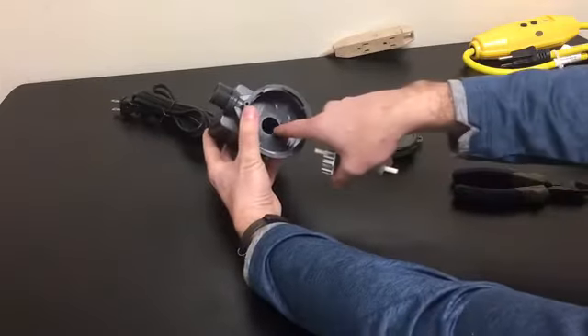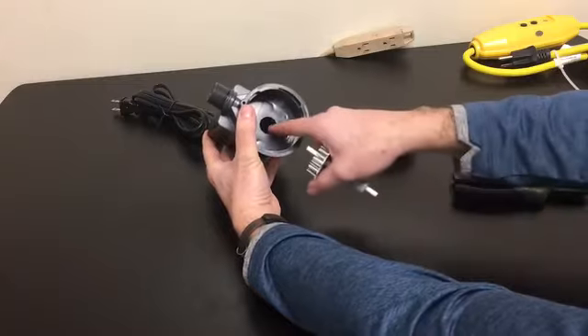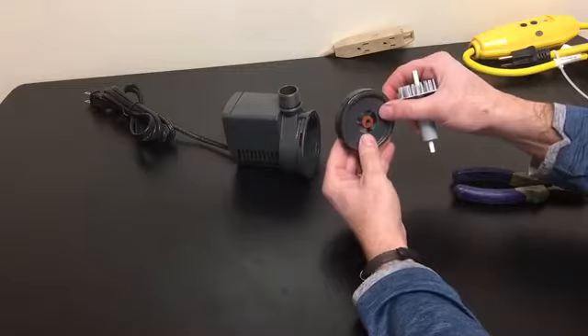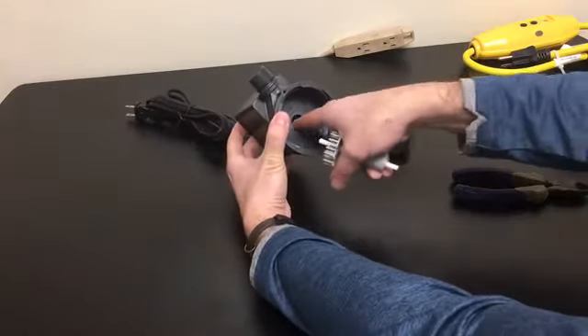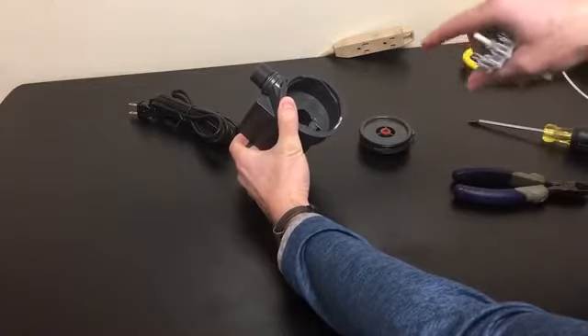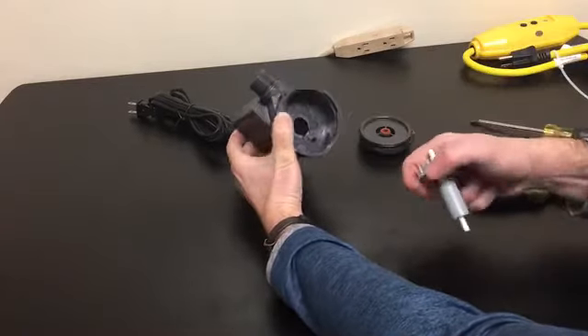You're going to inspect the rear bearing. Make sure it's good, it's seated, it's in place, and you're going to inspect the front bearing for the same thing. You would inspect this interior hole to make sure there's no scarring that is all the way through to metal. As long as it's not through to metal, you're okay.